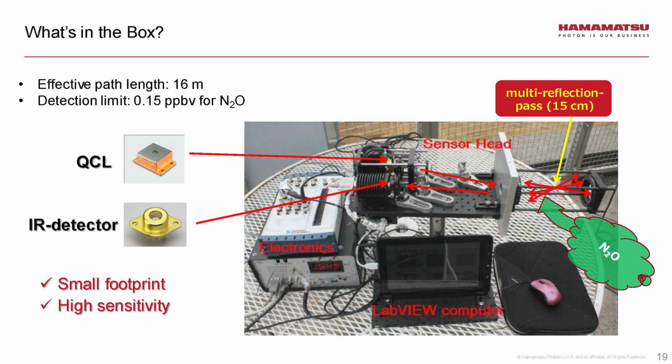This is essentially something that reflects the light back and forth many, many times. If you all recall, path length. Path length is absolutely key to achieving high sensitivity. So this is kind of what's going on. You got the detector, you got a multi-pass cell, and of course the laser, and you need a whole bunch of fancy stuff to power it. But of course, this is all miniaturized and optimized in the units that you see out there.